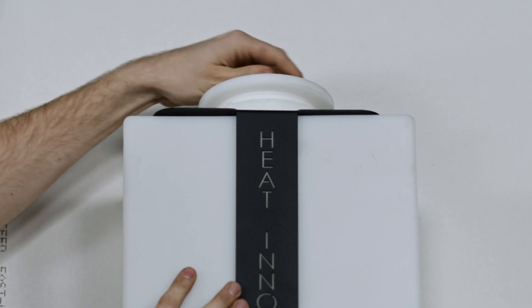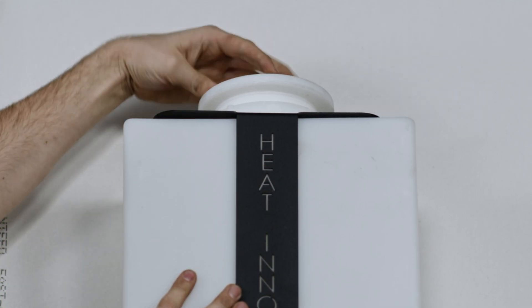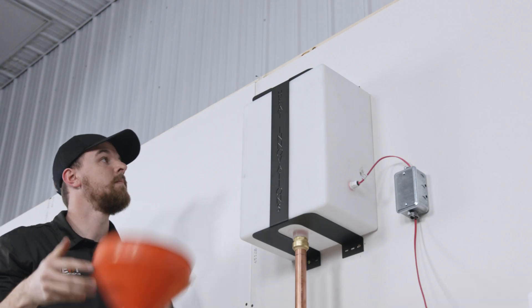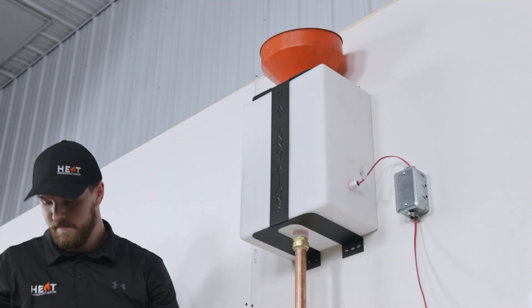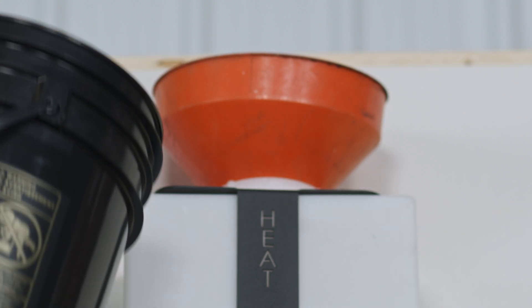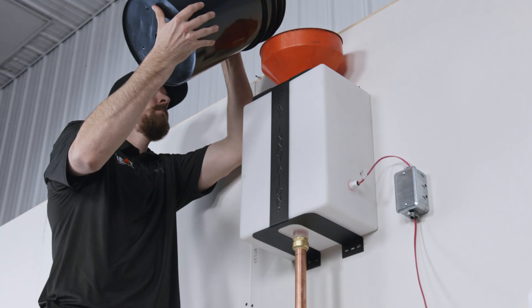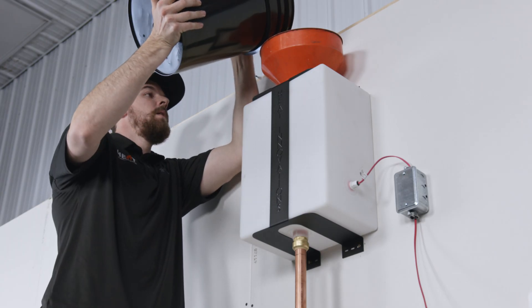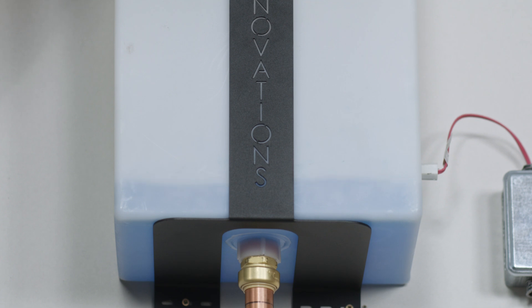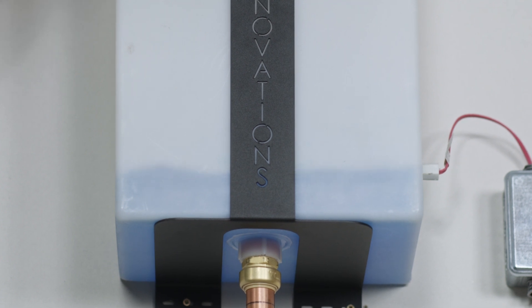Remove the lid on the expansion tank. With a funnel, fill the system with water and glycol mix through the expansion tank. We suggest a 30 to 35 percent glycol water mixture for most systems.